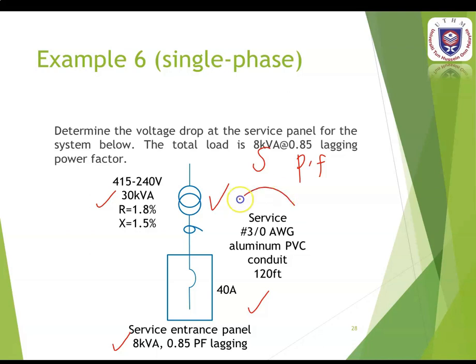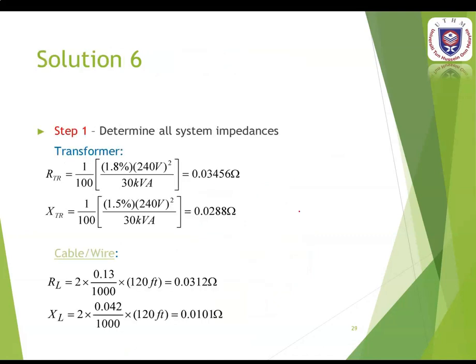This system uses a cable 3/0 AWG aluminum PVC conduit with the length of 120 feet. To calculate the percentage voltage drop, there are 5 steps to consider. The first step is to determine all system impedances. In this system we have two components: the transformer and the cable or wire.